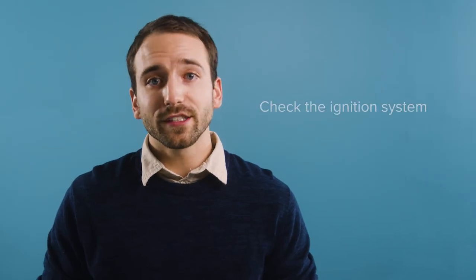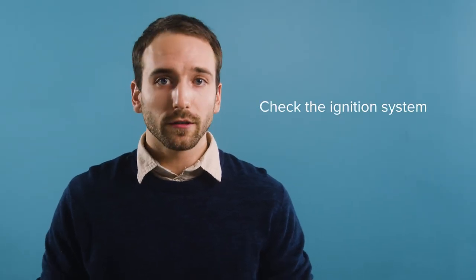Finally, if your furnace's ignition system isn't working properly and doesn't produce a flame within 4 seconds, the flame sensor will shut down the system. Again, we highly recommend that you get a professional to check this out if you believe this to be the case.